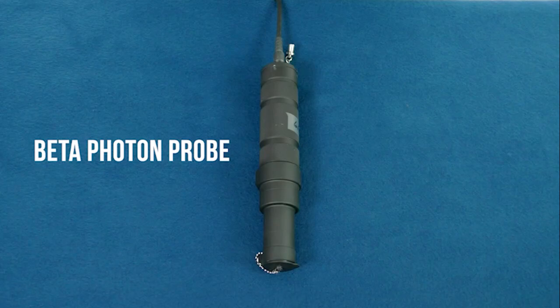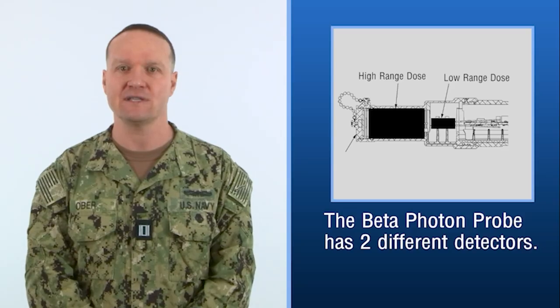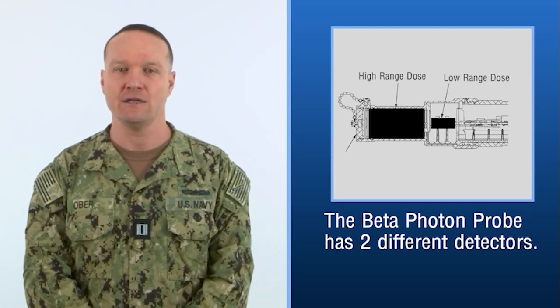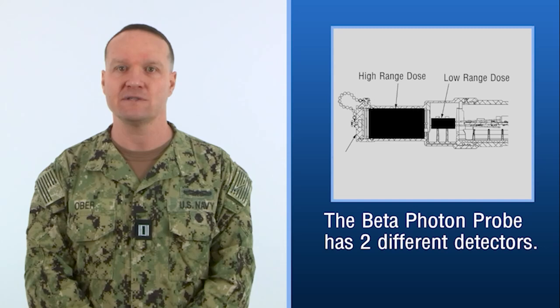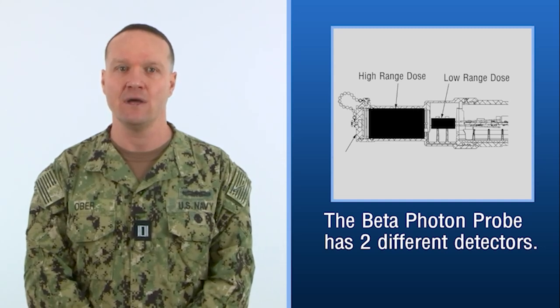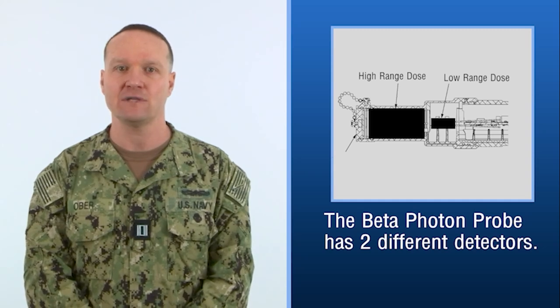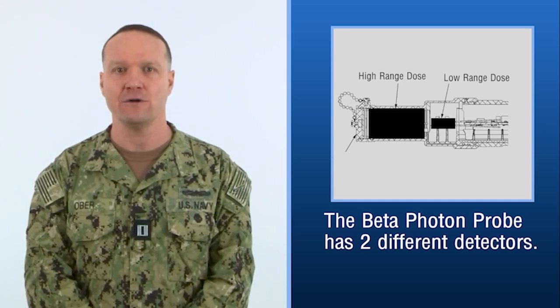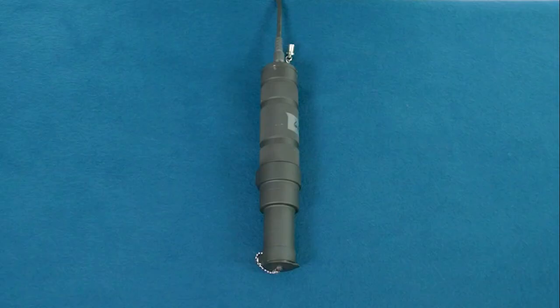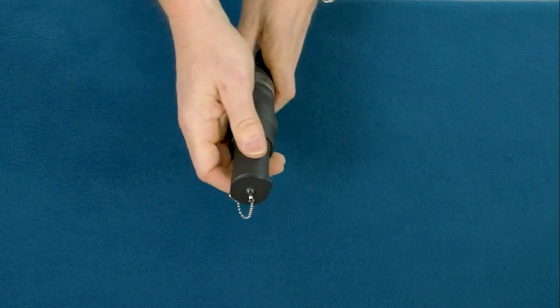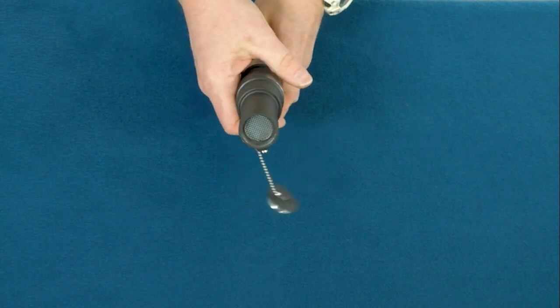Beta photon probe. The beta photon probe has two different detectors for low to high range dose and dose rate measurements. The low dose Geiger-Müller or GM tube is a gas-filled end-window detector sensitive to both photon and beta radiation with the beta window cap removed. The high range photon detection is achieved by a high dose GM tube. Removing the beta window cap at the end of the probe will increase sensitivity for beta radiation and low energy X-ray radiation. Similar to the base unit, here's the beta window, and here's how we remove it.